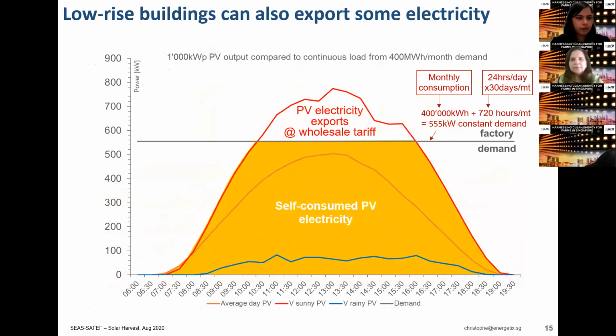The savings are determined by one more thing: how much you consume yourself at your avoided tariff, and how much you end up generating over and above your consumption, which gets exported at wholesale tariff—the price generators sell to the pool for, which is significantly lower. This example shows a building with a 400 megawatt hour monthly demand, a continuous load of 555 kilowatts, and a 1 megawatt peak rooftop system.